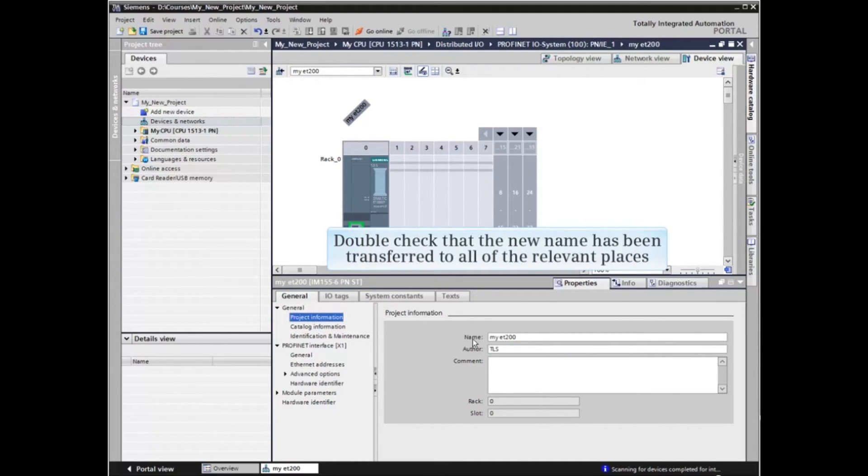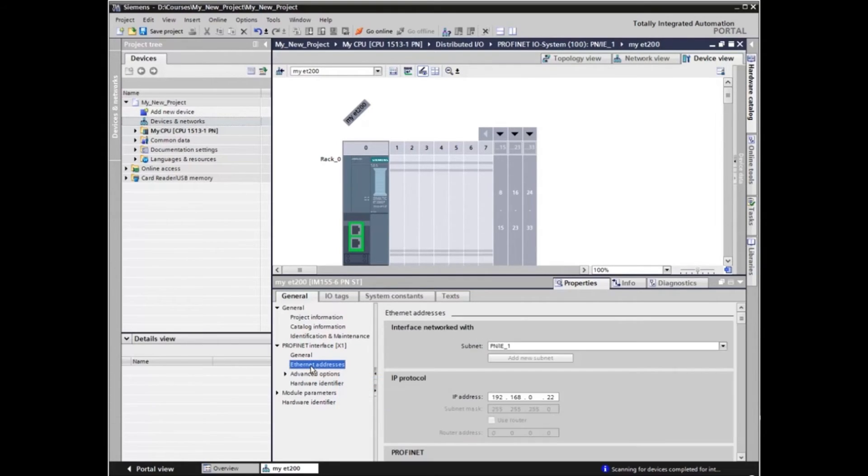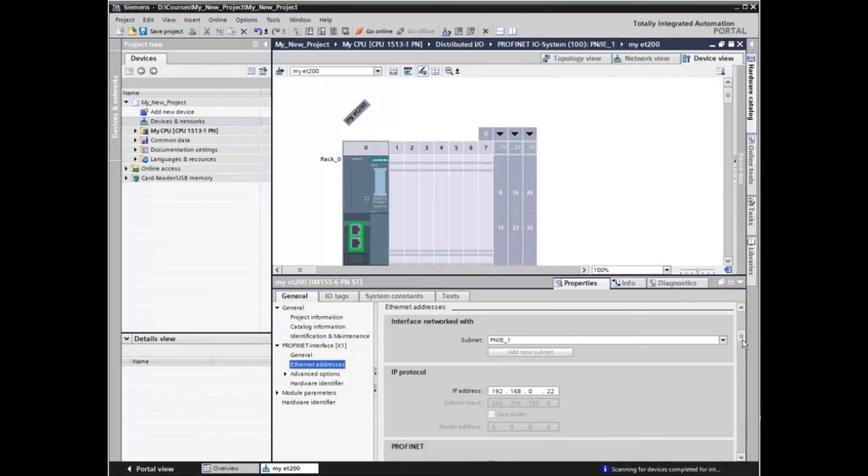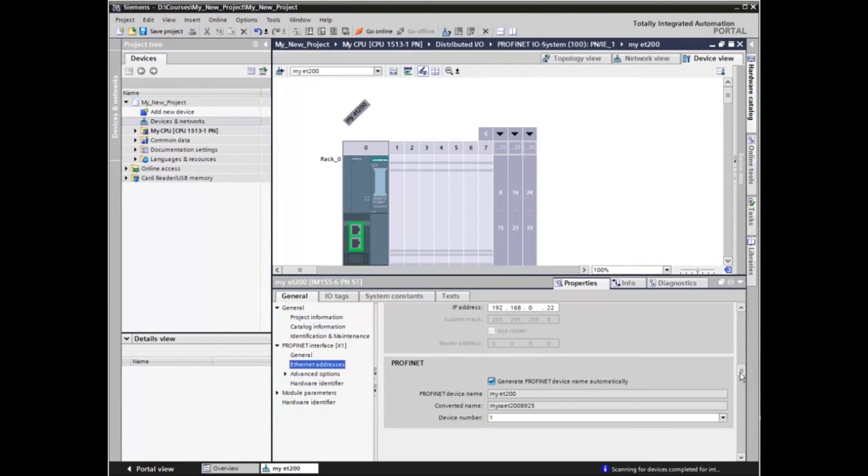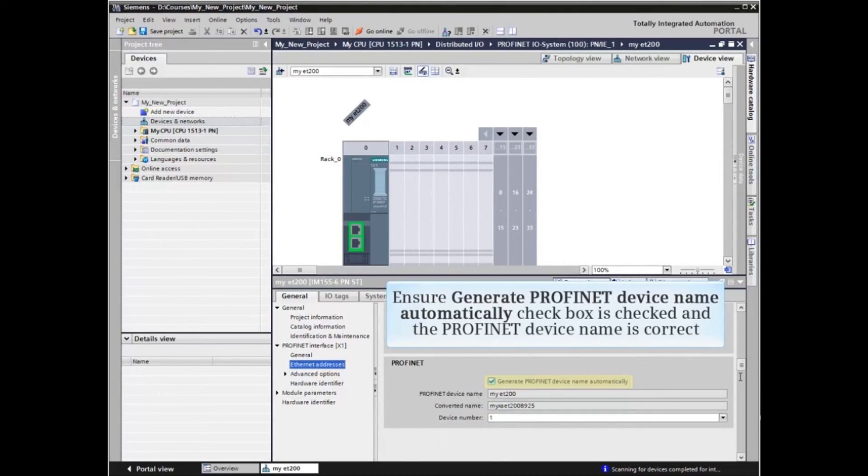Now let's double check that the new name has been transferred to all of the relevant places. Click Ethernet addresses once again from the menu tree. Scroll down to the PROFINET heading and ensure the Generate PROFINET device name automatically checkbox is checked and that the PROFINET device name is correct.